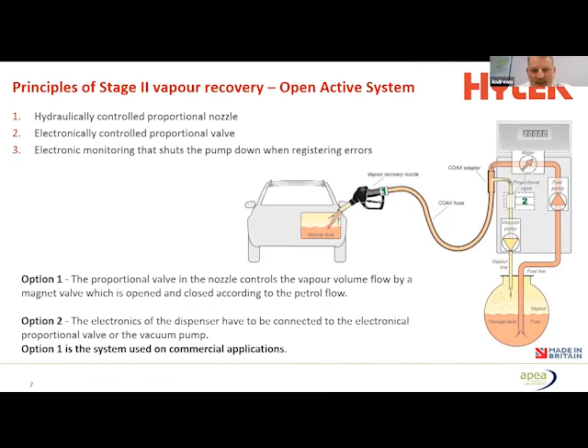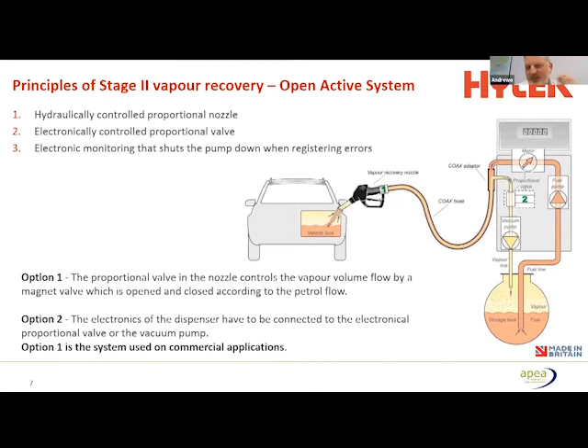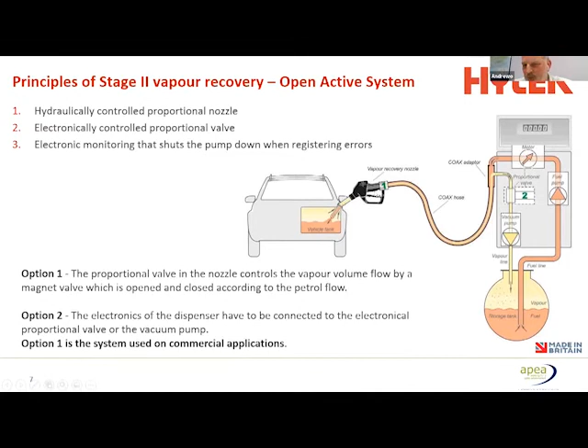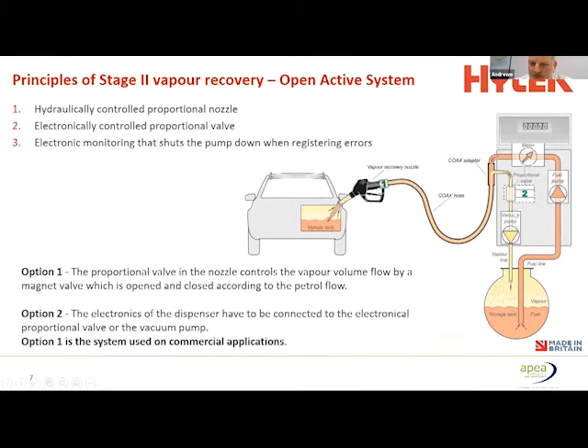In order to meet the 85% efficiency, there has to be a way of controlling and calibrating that. So there tends to be two ways of doing that. We can either use a proportional valve on the nozzle, and on this valve we can then calibrate. During calibration, we can open or close that valve. There is the option to have a proportional valve inside the actual fuel dispenser itself, which is then linked to the electronics. Generally, though, within the commercial sector, we would tend to use option 1 here, where we're using a proportional valve within the nozzle.